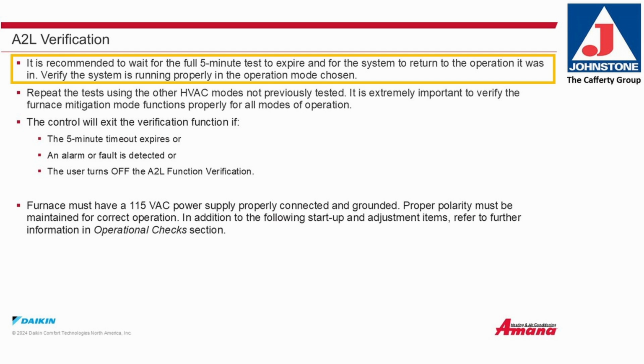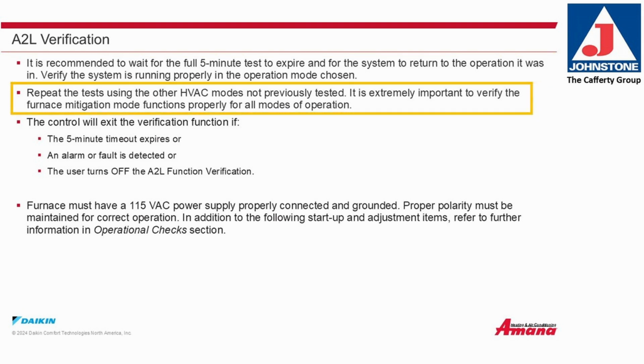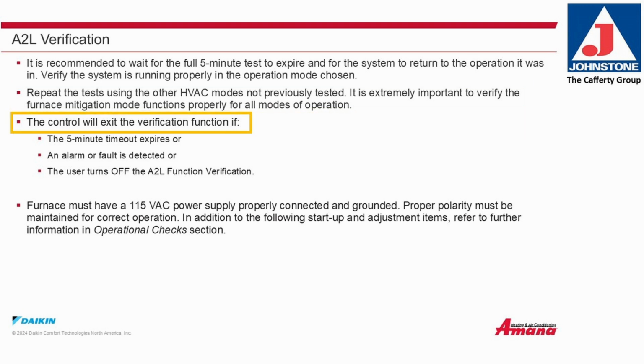It is recommended that you wait for the full 5-minute test to complete and for the system to return to the mode of operation it was in. Verify the system is running properly in the operation mode chosen. Repeat the test using the other HVAC modes if not previously tested. It is extremely important to verify the furnace mitigation mode functions properly for all modes of operation. The control will exit the verification function if the 5-minute timeout expires, an alarm or fault is detected, or the user turns off the A2L function verification.